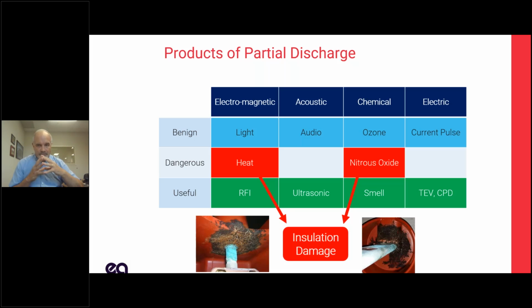And then there's this current pulse, right? We said PD is a current pulse. That has a variety of electrical effects that we can pick up. One is transient earth voltage. One is CPD or cable PD. It is a current. If we can measure that current, if we can put a transformer in place to measure that current, we can use that to detect PD, even though we may not be able to see it, hear it through ultrasonic, smell it, or anything else. So there's a variety of effects that are good, bad, and benign.